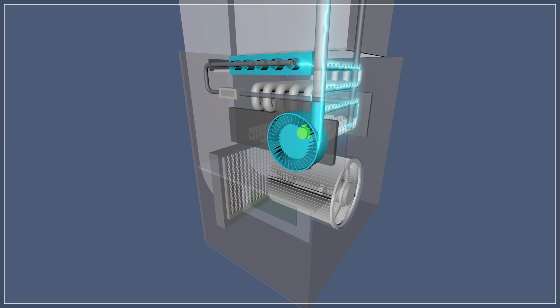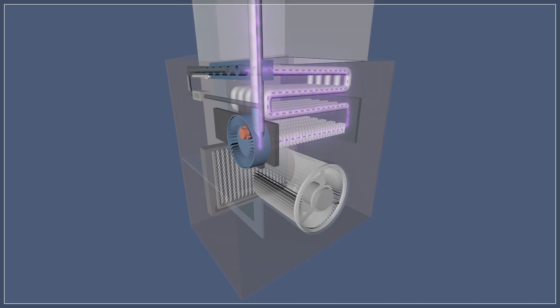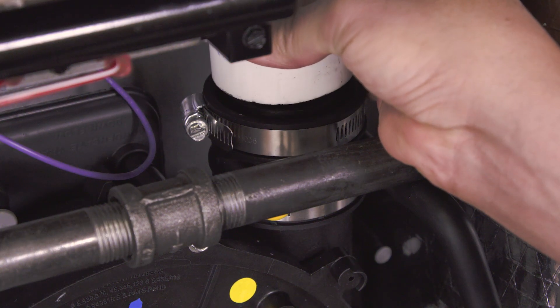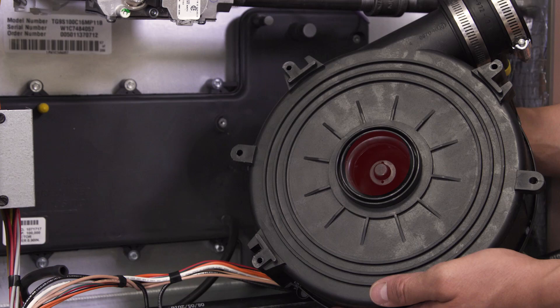If the inducer is running and there's enough airflow to remove the exhaust gases, then the pressure switch will close. When the pressure is low, the switch will stay open and will prevent the furnace from igniting. Try to identify anything that might cause a change of pressure inside the heat exchanger. Check to see if there's any obstructions in the flue vent or in the inducer motor port.